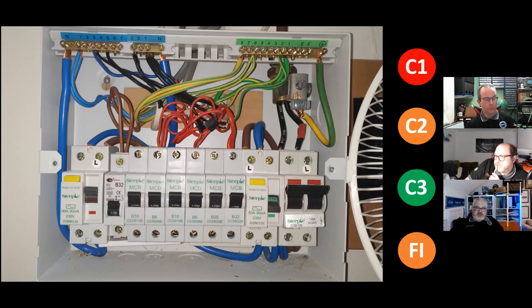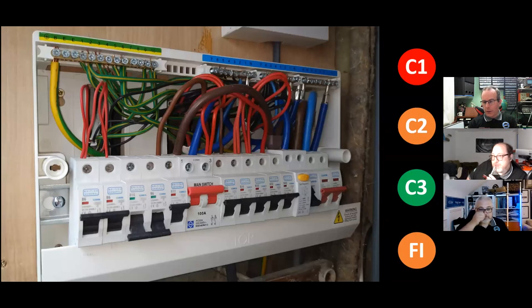But I would, just because of the pyro and the method of connection for earthing, because most codes around earthing are a C2, I would suggest that. It looks like there's a fan on the right-hand side of that board. If it's there and it's going to get knocked, it's going to suffer from vibration. That terminal could come loose. So for me, it's a C2 based on the earthing and termination of the gland. That's just a view of it. And also, yes, the sizes of the pyro, although pyro can carry far more than others, which is why a lot of the old buildings have got the submains wired in it. Yeah, there's a lot of little bits in this one, but the incoming was the main thing.